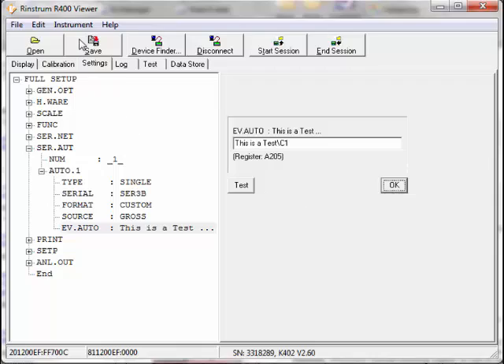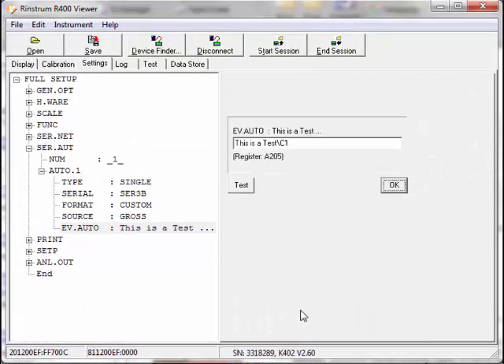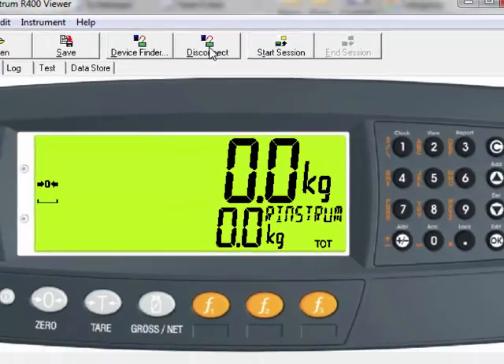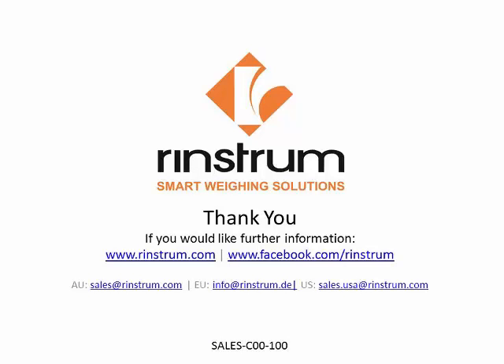Once the setup is complete, another powerful tool is the save function. The entire setup can be saved by file name with an RIS extension. This allows the complete setup to be saved for later use and deployment across many other units, or as a diagnostic tool. Once the file is saved, use the End Session button to close the session and then the Disconnect button to disconnect from the indicator. This completes the RIN-Link and Viewer 400 overview. This has been another Rinstrum educational series program. For more information, please visit www.Rinstrum.com or follow us on Facebook at forward slash Rinstrum. Thank you.